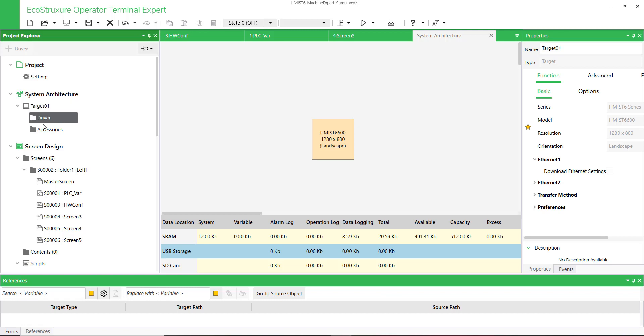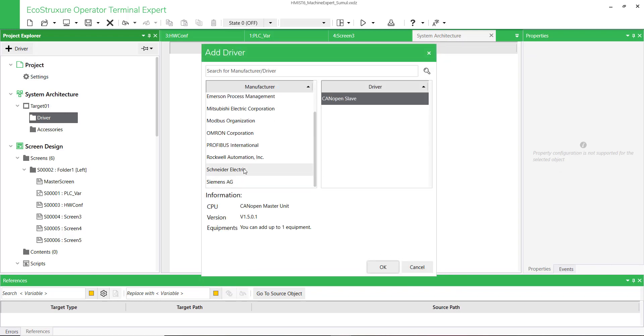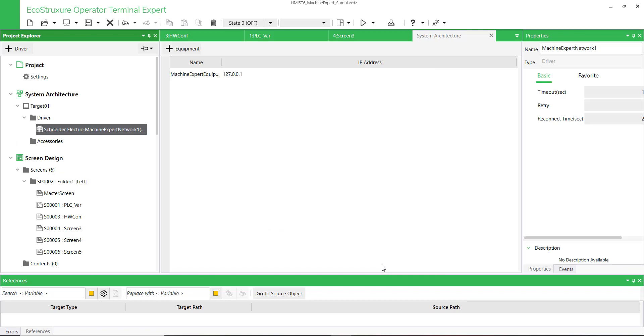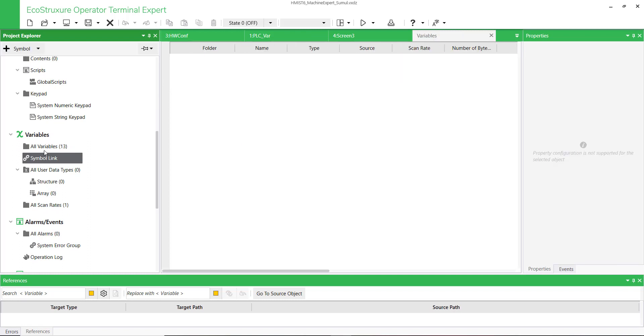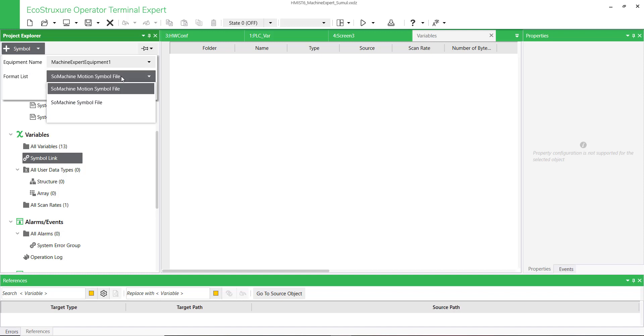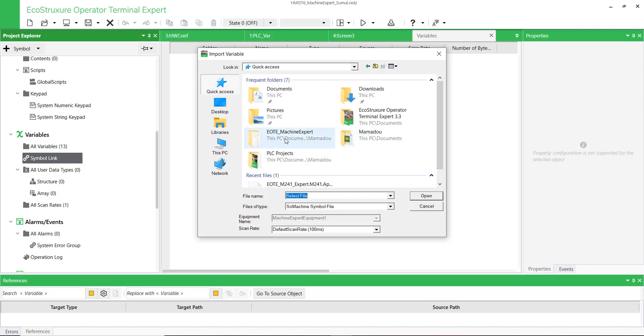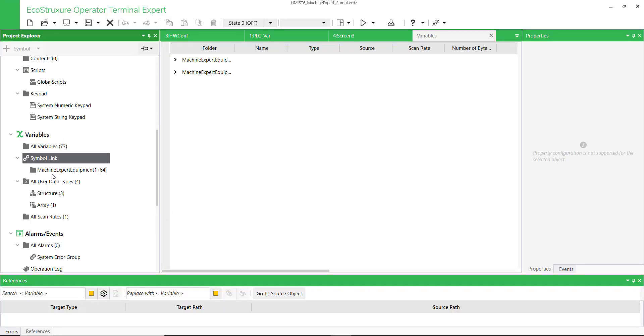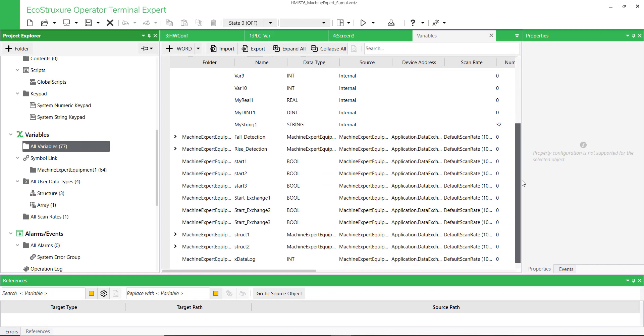Now let's switch to EcoStruxure Operator Terminal Expert to configure the HMI application. Click on Driver and add Machine Expert Network. Click on Symbol Link in order to import the PLC variables. Add Symbol Link and select the SoMachine symbol file. Select the XML file generated previously. Now you can see the PLC variables are imported.